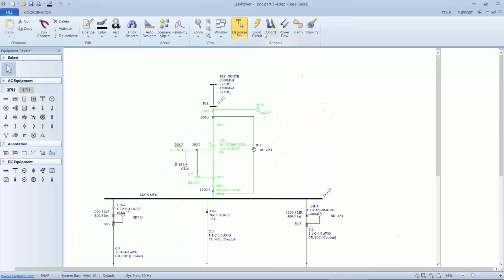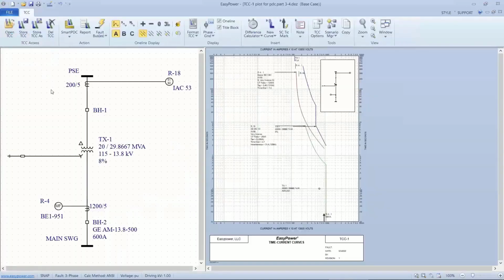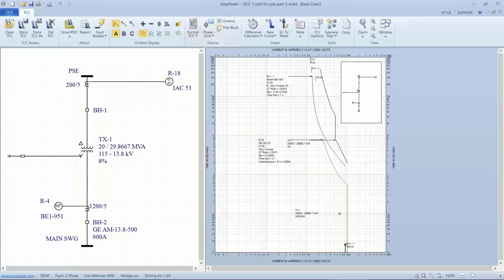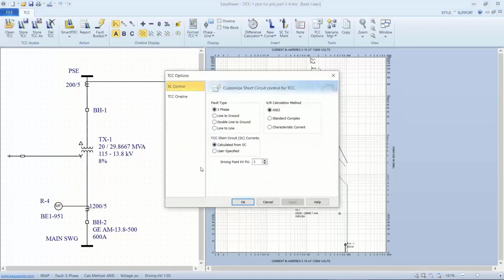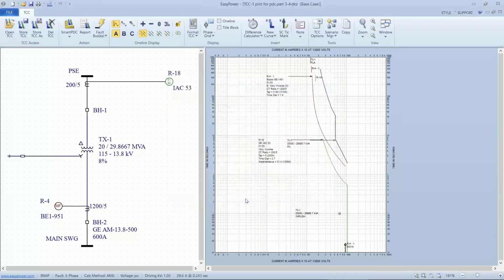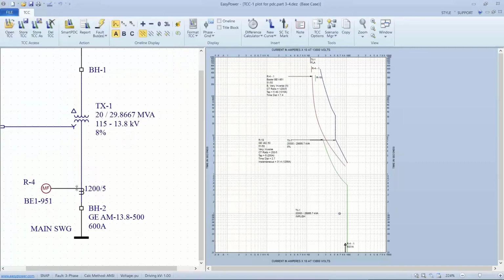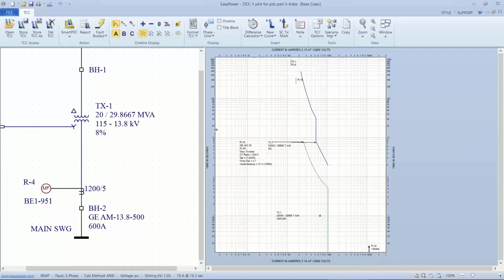By going to coordination, plotting the curve, we see something that looks like this. Now for grins, I'm going to turn off that. Well, first of all, I don't see any color on this TCC curve. I'm going to right-click, TCC options, and I want on my one line to sync the TCC colors to the TCC plots. Once we do that, we see kind of a rust color on this downstream secondary relay. And so that's this curve right here. So let's delete that just to not confuse the situation. Next, I want to talk about the transformer.